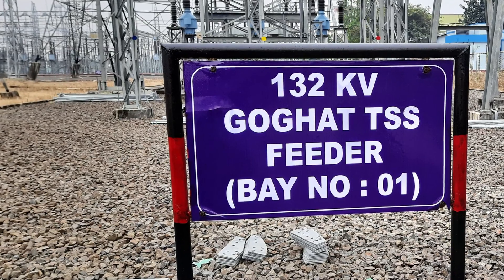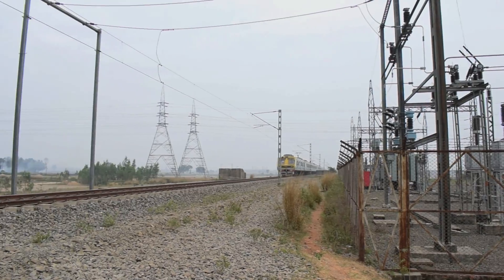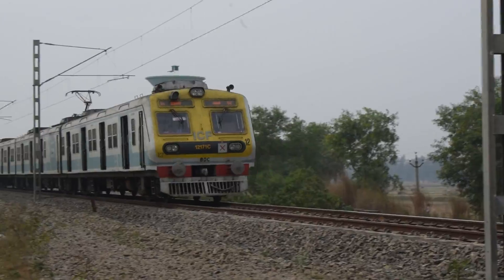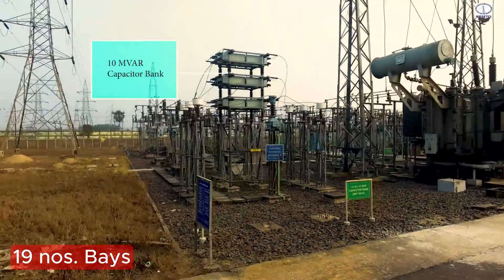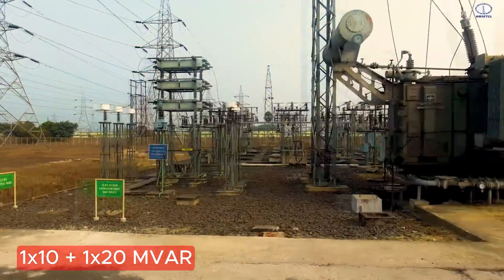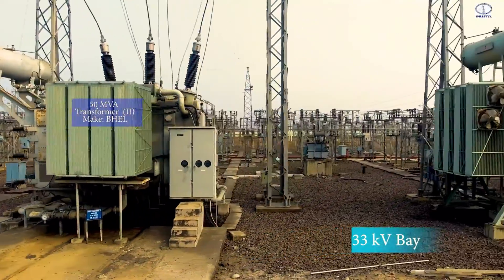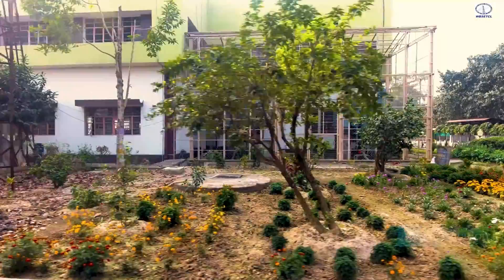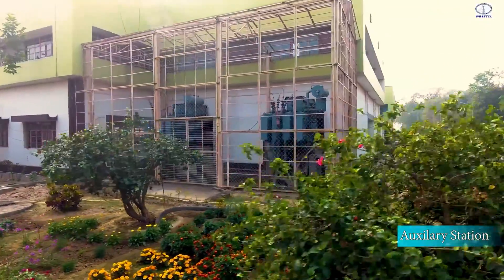Another important 132 KV bay is Goghat TSS. This traction substation draws power from Arambagh substation via a 132 KV single circuit. For the 33 KV voltage level, total 19 bays are there including 2 capacitor bank bays. Three numbers of 50 MVA transformers are installed in the 132 KV by 33 KV system. Two numbers of 1.5 MVA transformers are used as station service.